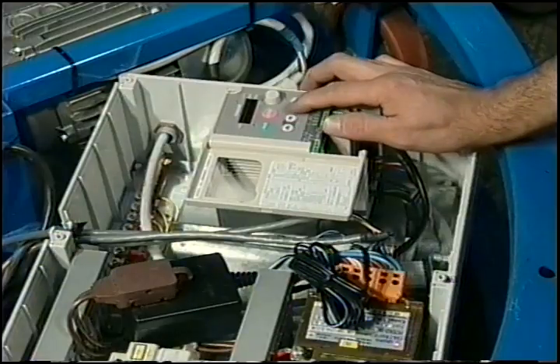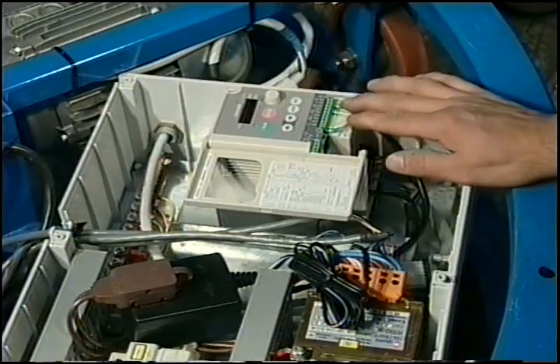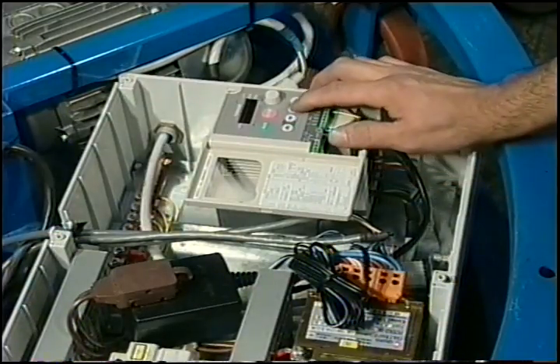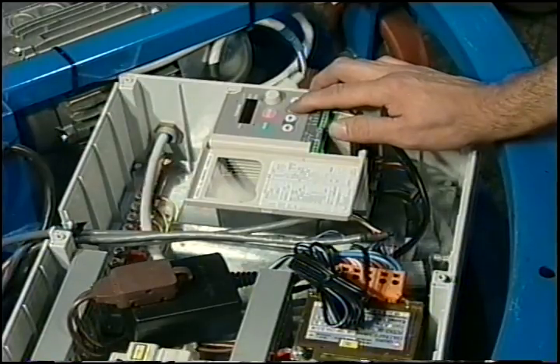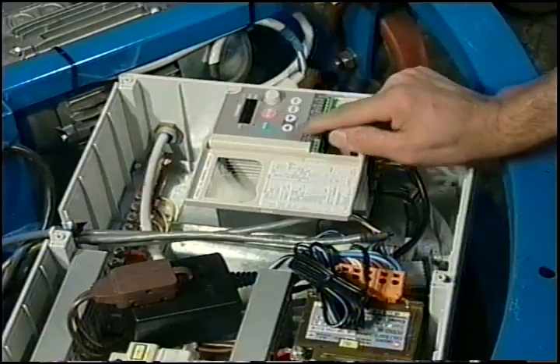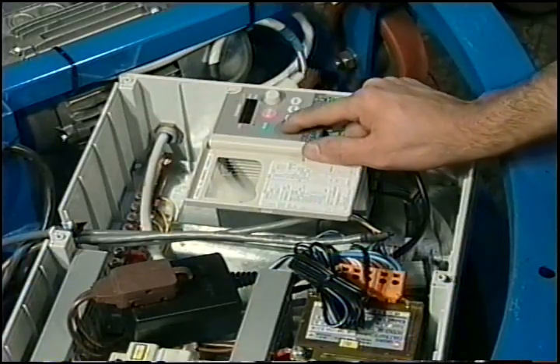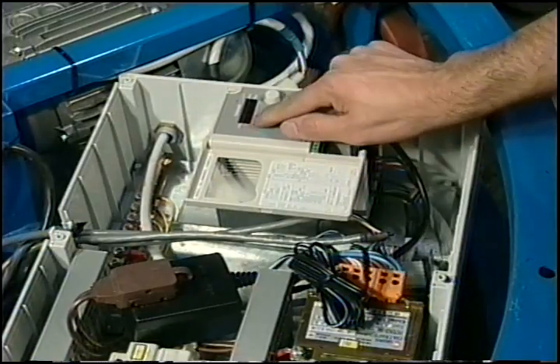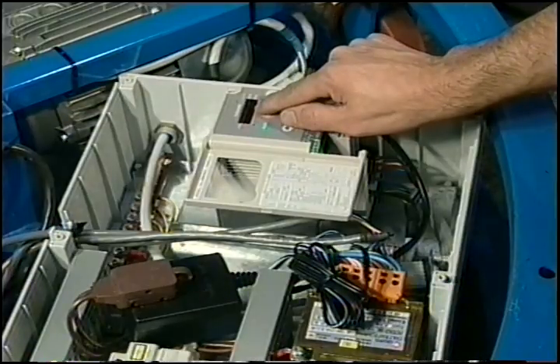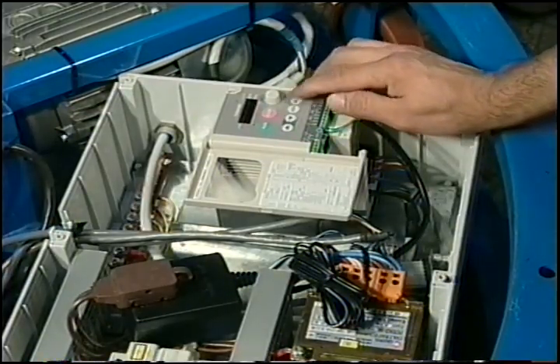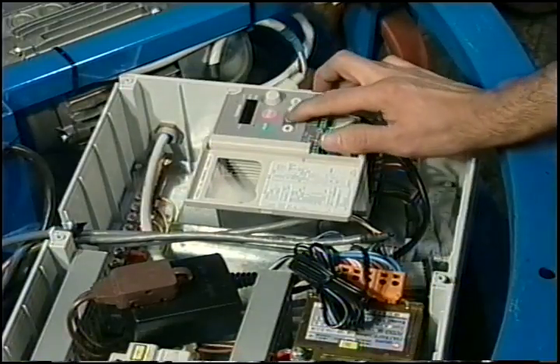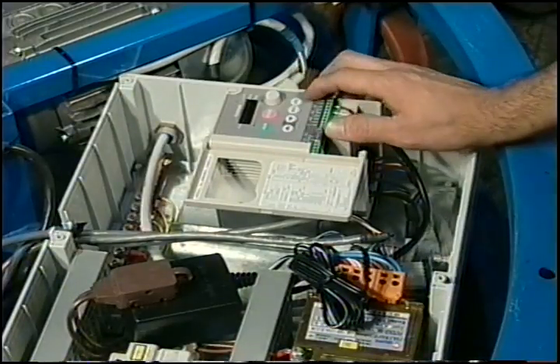if you have that command on 1, it's no longer going to see these inputs anymore. So you want to be sure that after you make those settings, you hit the MON button once, hit the arrow button 4 times. You're going to see the command on your display say CNOD. You can hit enter. It's going to show the value of 1. Hit the down button, value of 0.